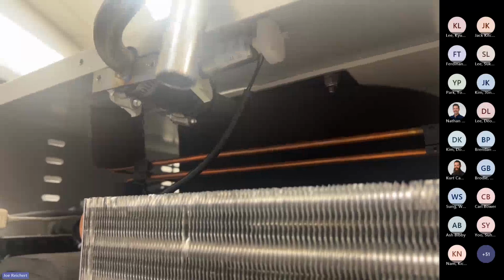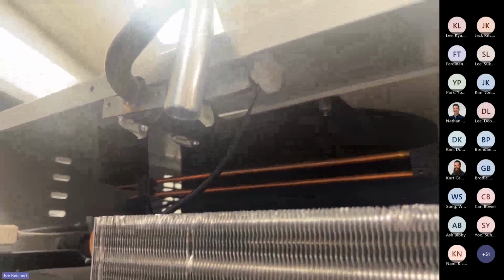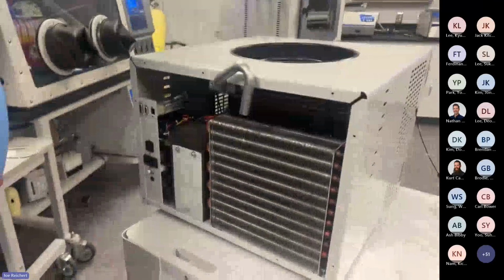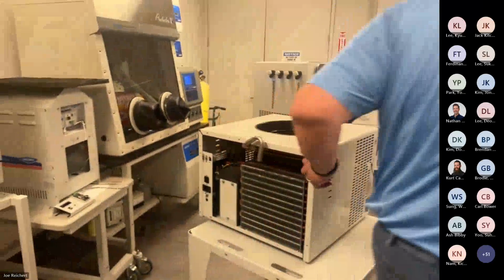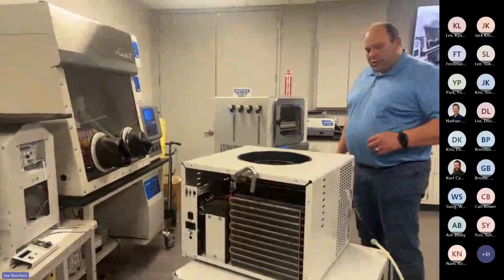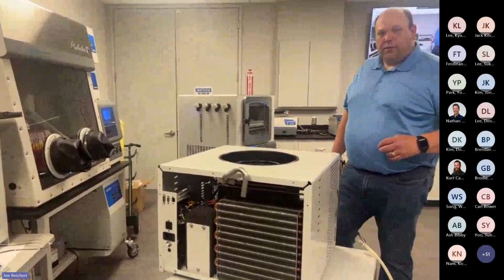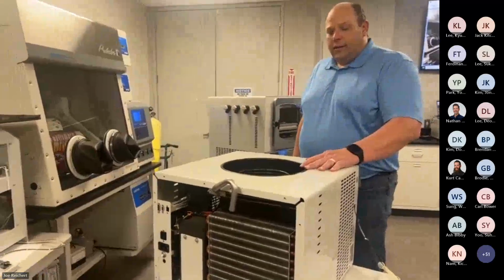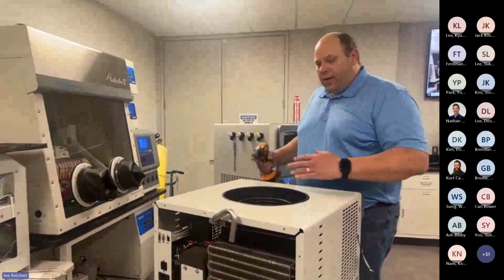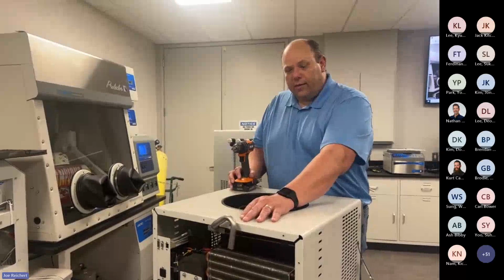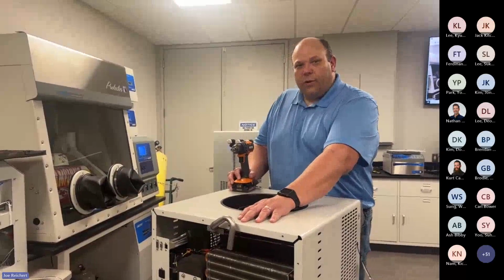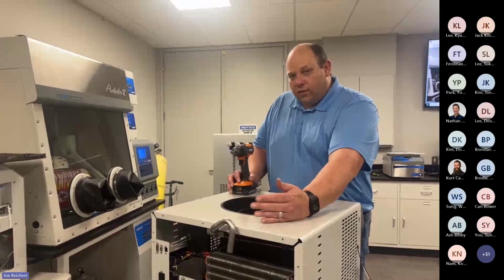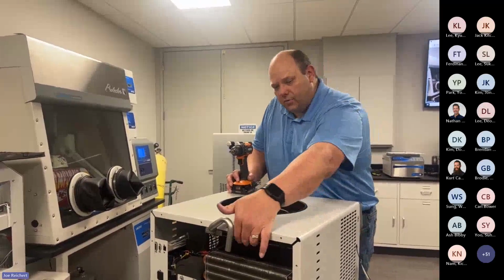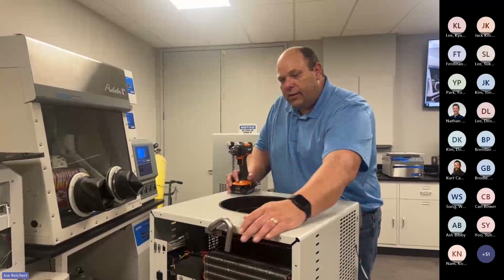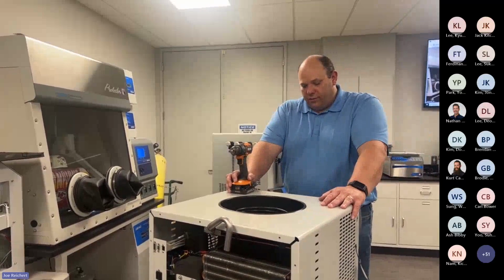I do get pictures of that a lot from customers and service providers looking for the vacuum sensor, and they send me that picture thinking that that's the vacuum sensor, but that is not. It is the vacuum release valve. And it is possible for that valve to leak. It's supposed to close as soon as you turn the vacuum on. It can stay open if it is broken, but you'll know that when it's broken. If you can't get a vacuum, if you put your stopper in this hole in the back and you still can't get vacuum, but you know your vacuum pump is good, well, your only two options at that point is either the vacuum sensor or the vacuum release valve. And sometimes if you just feel on the very edge of that filter on the vacuum release valve, you'll feel air pulling through it if it's what the issue is.